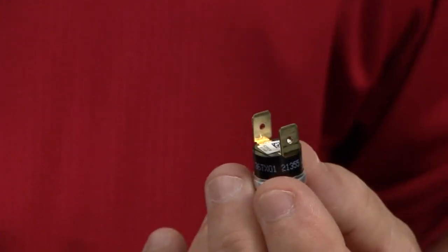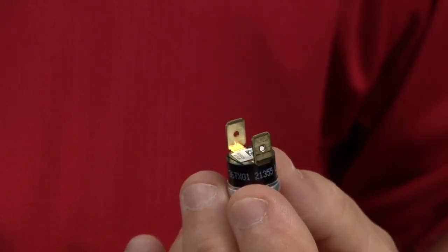A balance point thermostat is completely different than this thermostat. A balance point thermostat would shut off the outdoor unit if it was deemed that the heat pump couldn't keep up because it was so cold outside, and it would only allow the backup heat to function once it fell below the setting of that balance point thermostat. That's kind of old school, because in today's world, you really don't need a balance point thermostat in the outdoor unit, because you can use a good quality thermostat that's got an outdoor sensor, and then you set up the thermostat to whatever temperature you want the heat pump to shut down, and then the backup heat takes over. So it's pretty simple. You really don't necessarily need a balance point thermostat anymore.